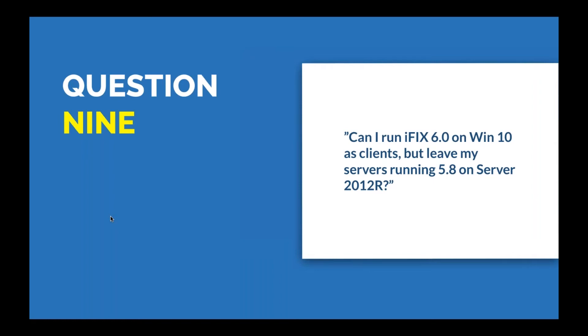Scott notes it's actually a two-part question—a mixed operating system question and a mixed version question for iFIX. As long as the clients need to be updated before the node, you couldn't do the reverse. You can't run a 5.8 client and upgrade your server to 6.0. But as stated before, your clients can be the latest iFIX and they can still communicate to your older SCADA node. That was kind of a trick question, but it's a two parter.